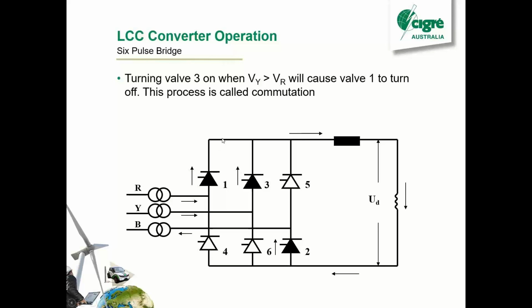And if everything's right and the AC waves that you're feeding the converter with are nice and balanced, once the yellow phase voltage exceeds the red phase voltage, it will cause the current in the thyristor to go to 0 and turn it off. If that happens successfully, that's called commutation. Going from one valve to another is commutation. So all's gone well and 1's turned off. Now we're operating with valves 3 and 2, and then we'll wait another 60 degrees.